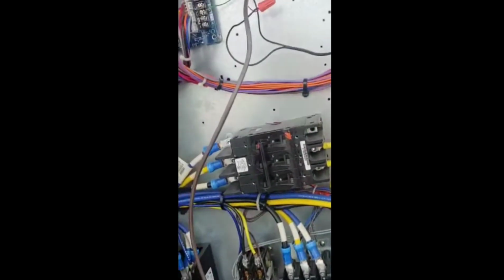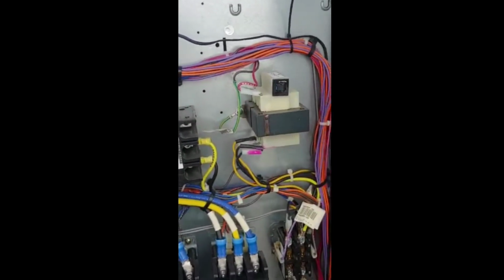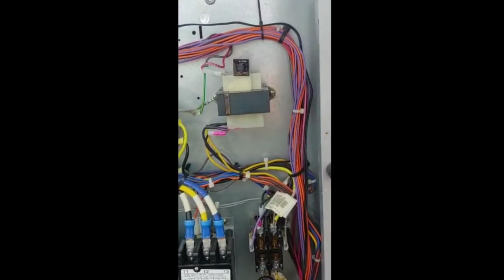Normally it's on the low voltage side, so I have to follow all the wires. Most of the time it's where a wire is rubbing, and I found it to be rubbing right here. Sorry about the noise, but the compressor - as you can see there, those marks next to the pressure sensor, those two little white spots - that's where the wires were rubbing.